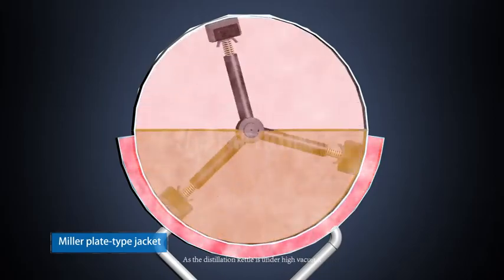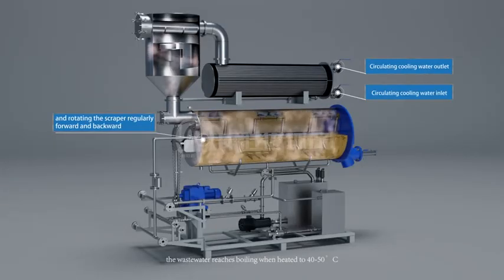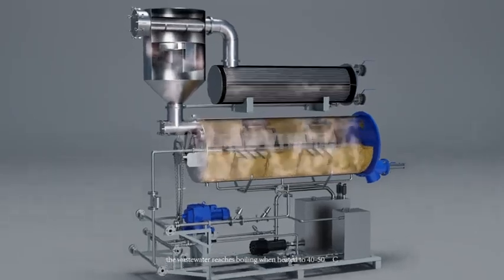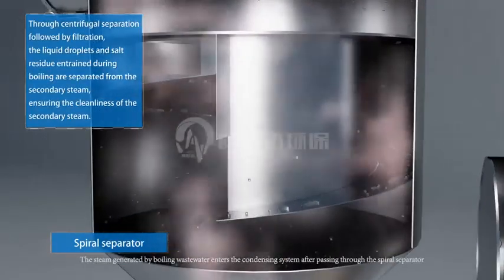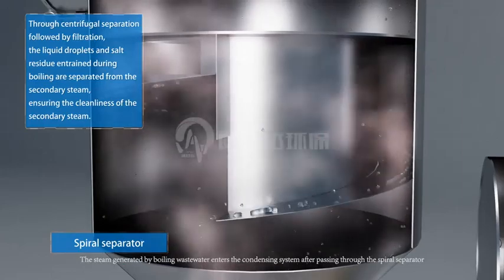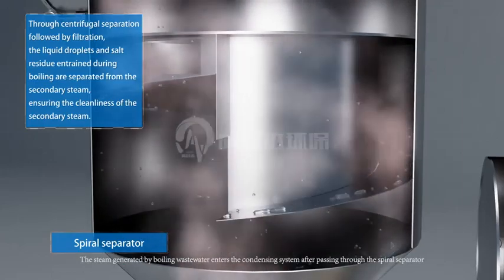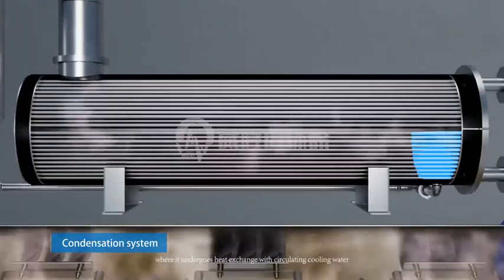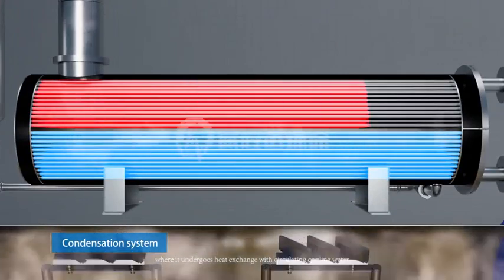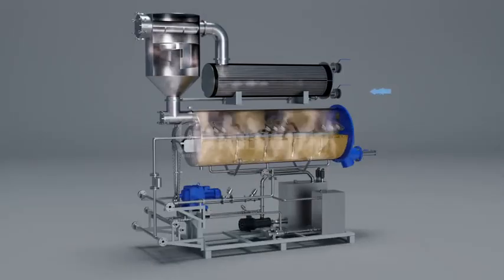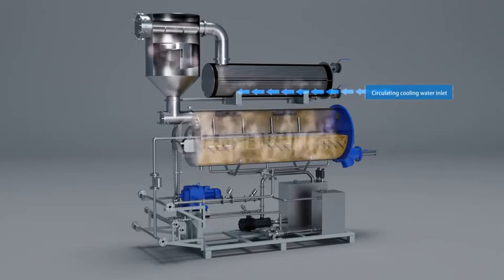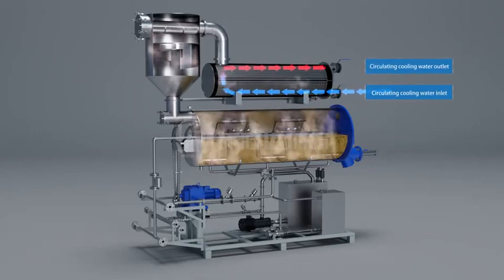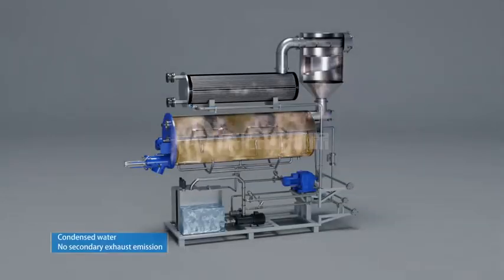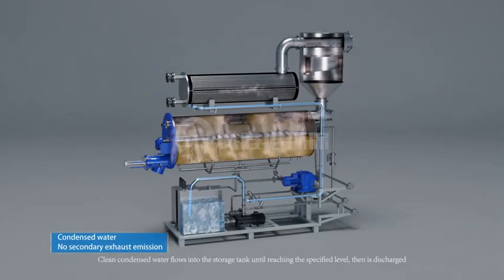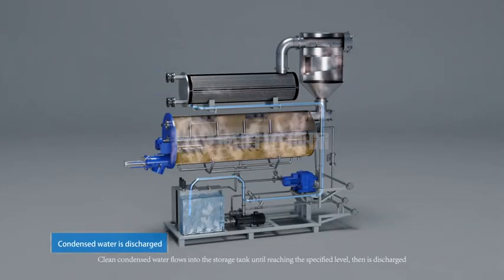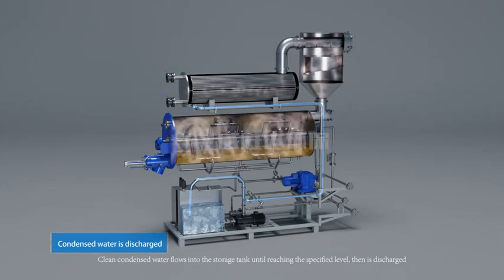As the distillation kettle is under high vacuum, the wastewater reaches boiling when heated to 40 to 50 degrees Celsius. The steam generated by boiling wastewater enters the condensing system after passing through the spiral separator, where it undergoes heat exchange with circulating cooling water. Clean, condensed water flows into the storage tank until reaching the specified level, then is discharged.